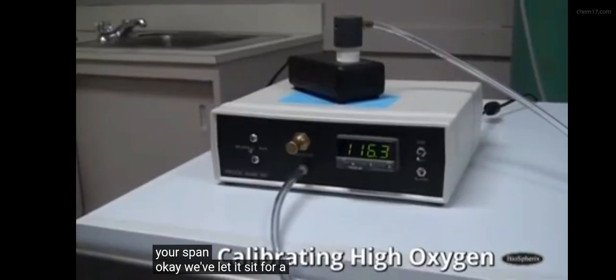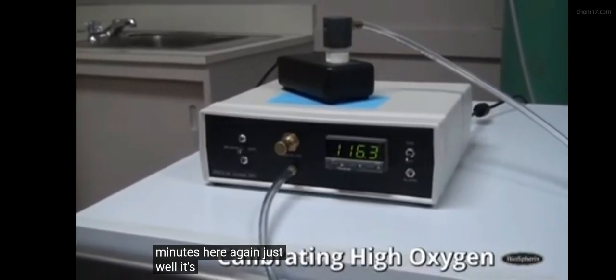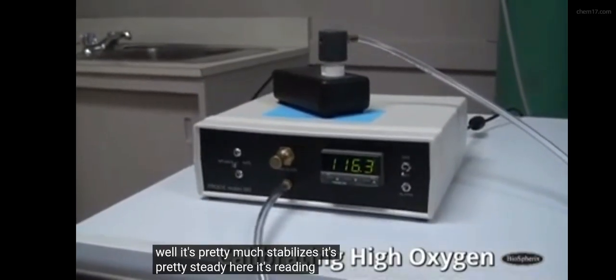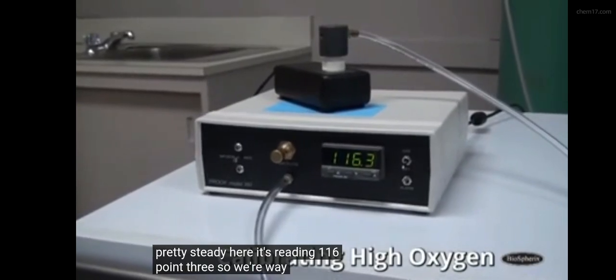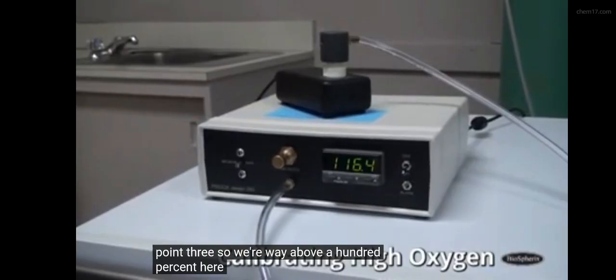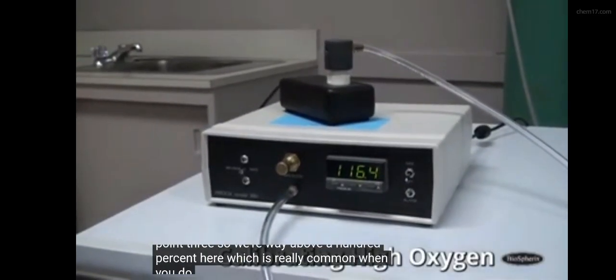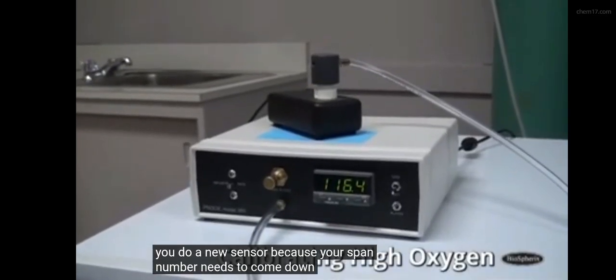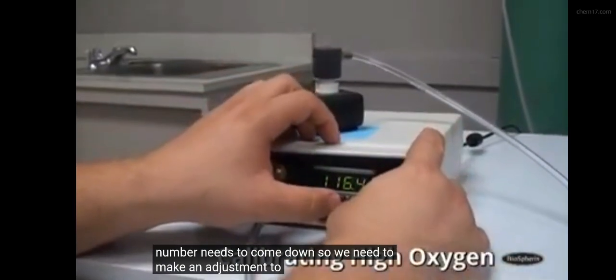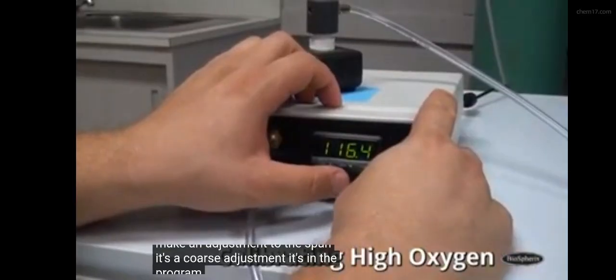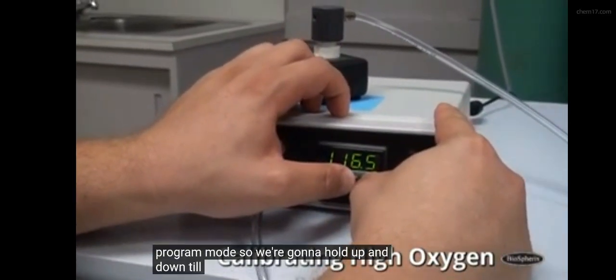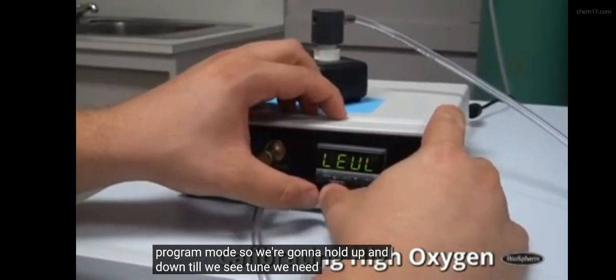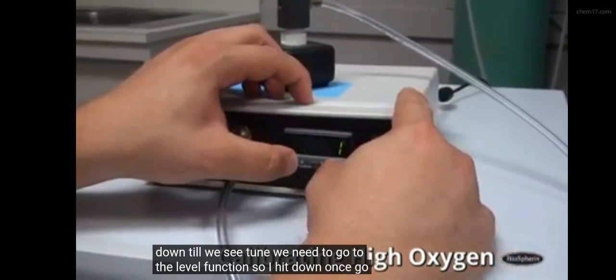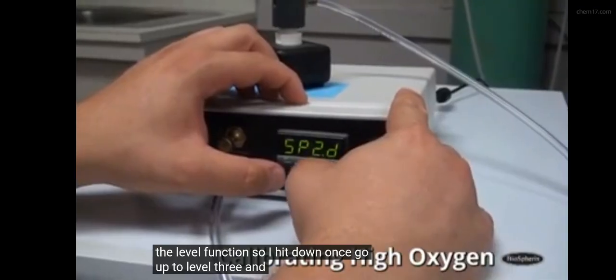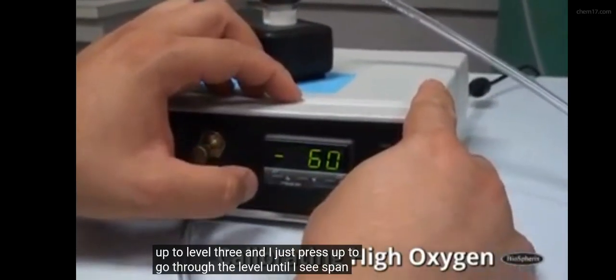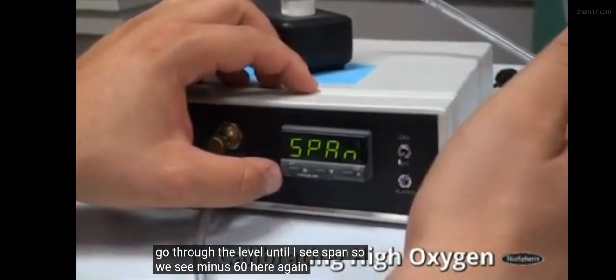Okay, we've let it sit for a couple minutes here. Again, you just want to let it sit till it pretty much stabilizes. It's pretty steady here. It's reading 116.3, so we're way above 100% here, which is really common when you do a new sensor because your span number needs to come down. So we need to make an adjustment to the span. It's a coarse adjustment. It's in the program mode, so we're going to hold up and down until we see tune. We need to go to the level function, so I hit down once, go up to level 3, and I just press up to go through the level until I see span. So I see minus 60 here.